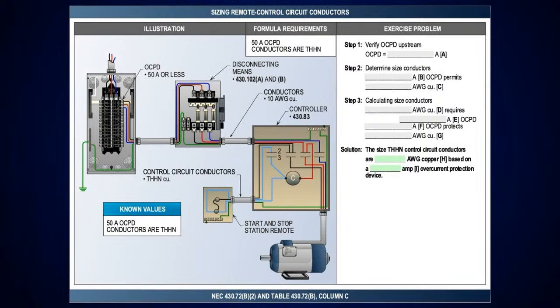Now, if you look at this illustration, see where I've got the control circuit conductors, but where are they going? They're going to a remote start and stop station. That's why you're not using table 310.17, because you've got those control conductors going over there in a conduit. And that's why we're using table 310.16. And then just do your exercise problem and put the 50 amps in there, and once you go over and look at the table, it'll tell you what size conductor, and then based on that amperage, you'll calculate it at 300%. Whereas if I was in the controller itself, I would do it at 400% because it's open air.